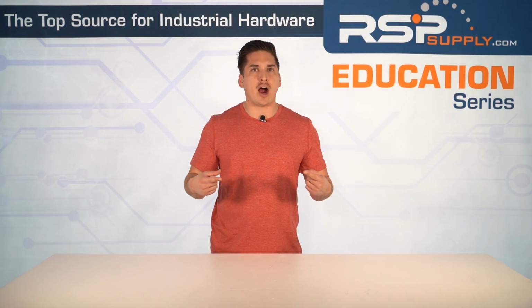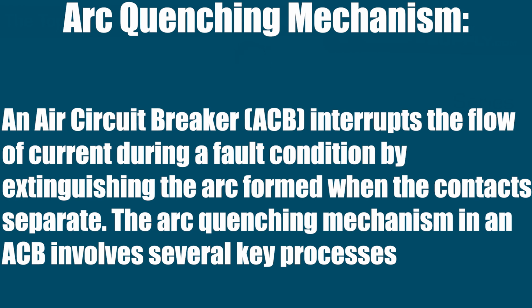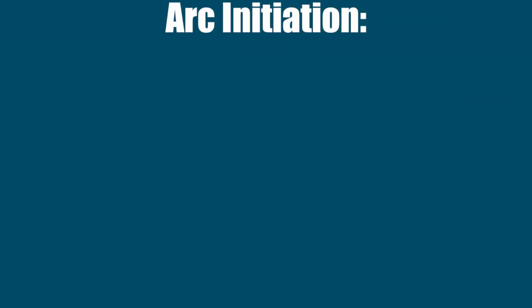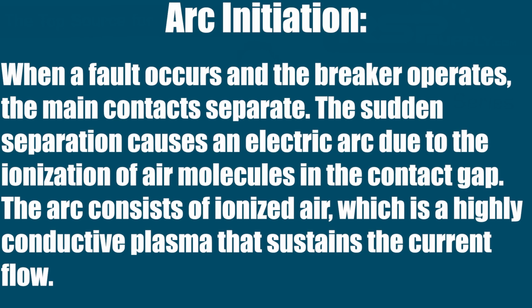Let's dig deeper into the unique arc quenching mechanism inside of an air circuit breaker. An ACB interrupts the flow of current during a fault condition. It does this by extinguishing the arc formed when the contacts separate. The arc quenching mechanism in an air circuit breaker involves several key processes. First off, there's the arc initiation. When a fault occurs and the breaker operates, the main contacts separate. The sudden separation causes an electric arc due to the ionization of air molecules in the contact gap. The arc consists of ionized air, which is a highly conductive plasma that sustains the current flow.